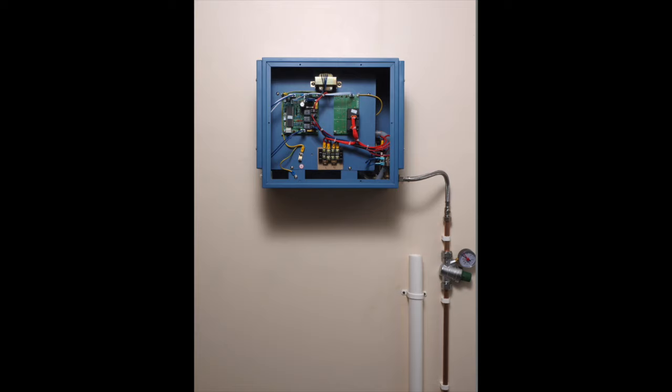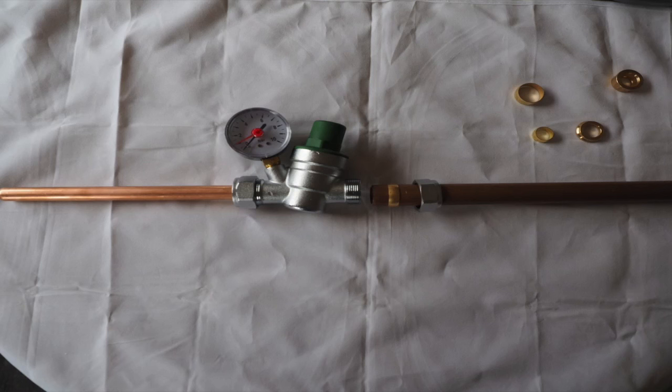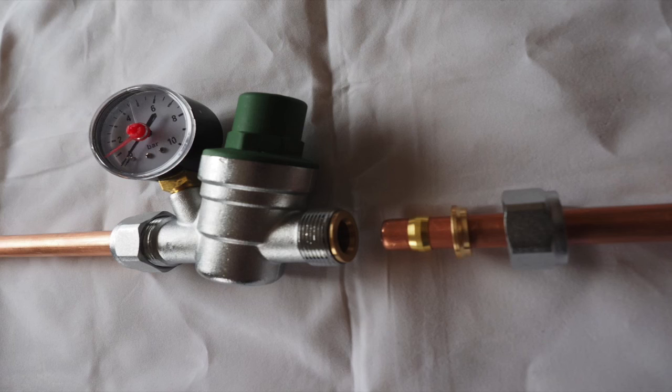There should be a pressure reducing valve in front of the steam generator on the water supply. This should be set at a maximum of one bar. Set the pressure when the water is flowing. Most pressure reducing valves will come with a 22 millimetre or 15 millimetre conversion kit.